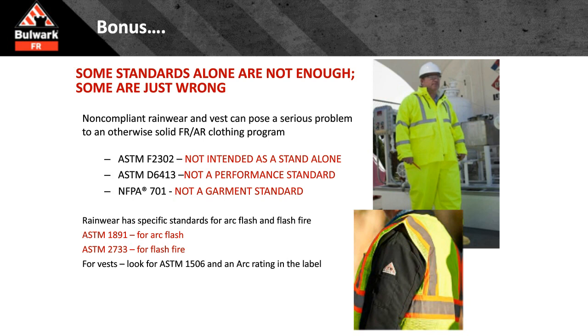It's a predecessor to doing a whole ton more work in order to get the right stuff. NFPA 701, most of you have heard of, is not even a garment standard. It's a drapery standard and a linen standard. The right ones for arc flash are ASTM 1891 for rain gear and ASTM 2733 for flash fire rain gear. In our high-vis vest world, look for ASTM 1506.